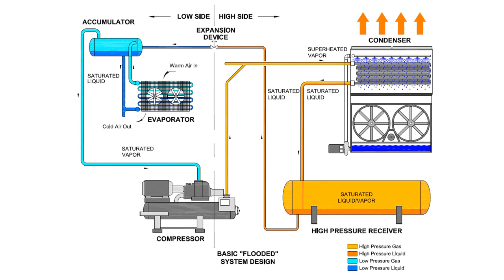The purpose of the condenser is to reject the heat absorbed in the evaporators and compressor to the atmosphere. The evaporative condenser receives high-pressure, superheated vapor from the compressor and supplies high-pressure liquid to the high-pressure receiver. The condenser uses air and water to cool the warm ammonia as it passes through a series of tubes within the condenser. Water is contained in the sump of the condenser, which is then pumped and sprayed over the ammonia coil. As the cooling medium of air and water draws the heat from the vapor, the refrigerant condenses into a liquid and flows to the high-pressure receiver.